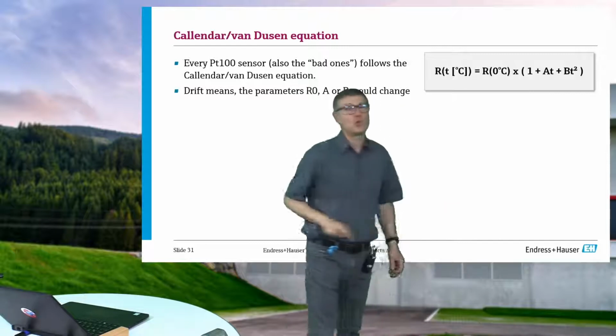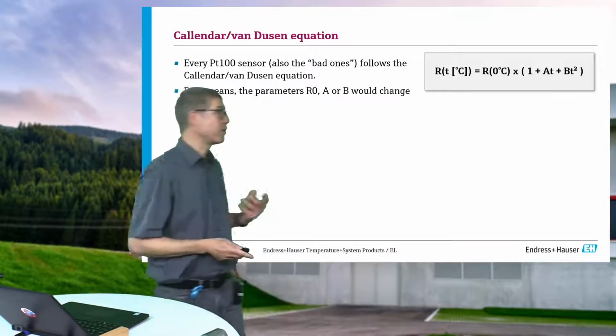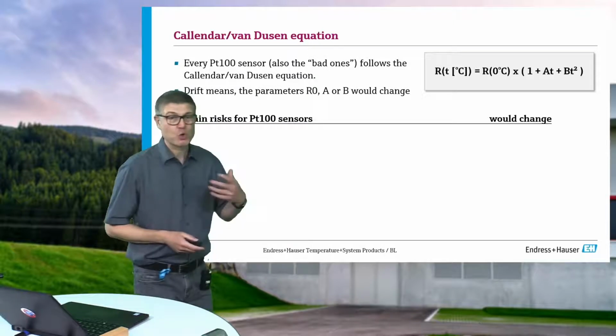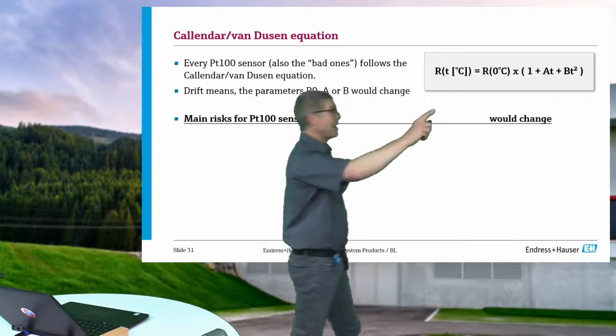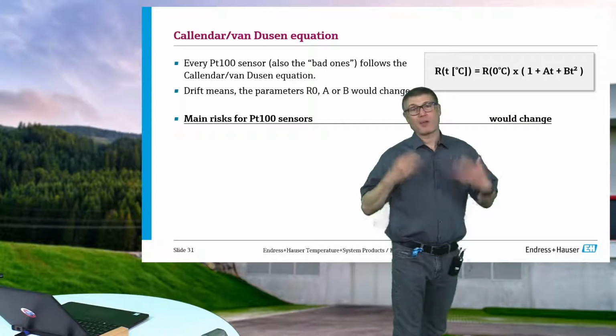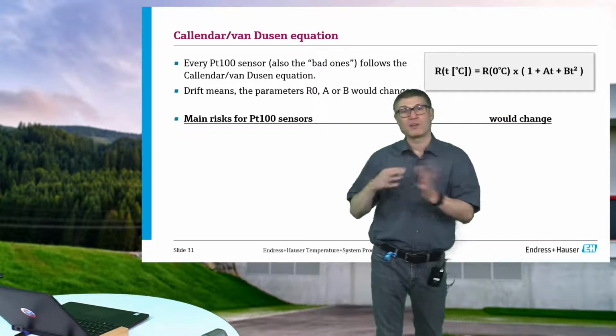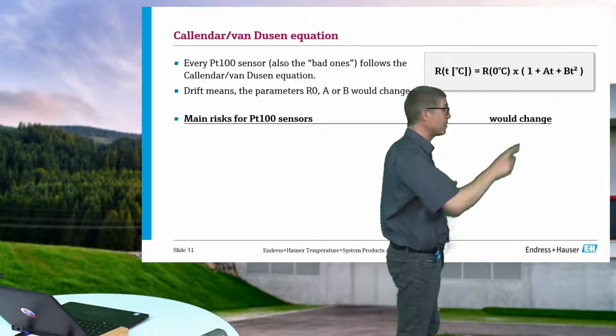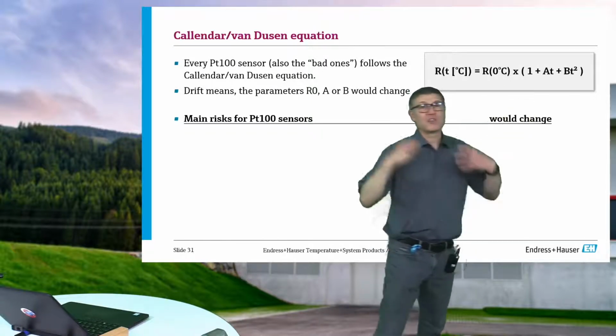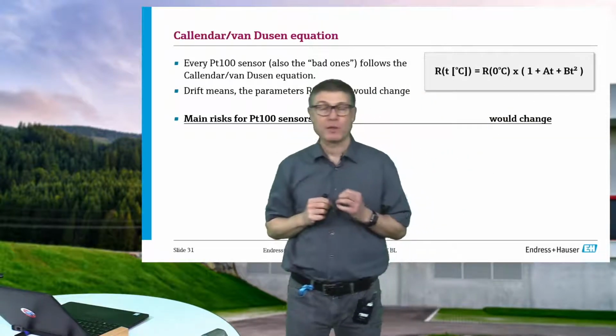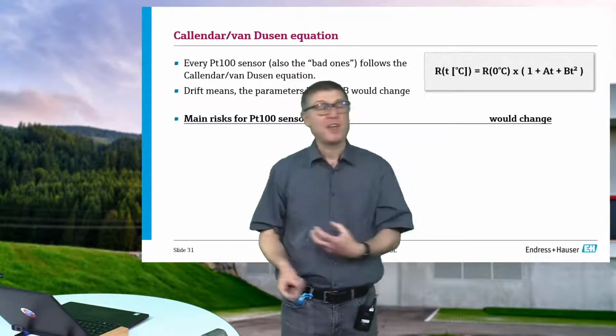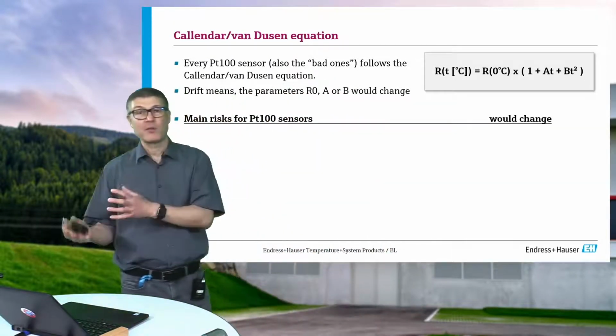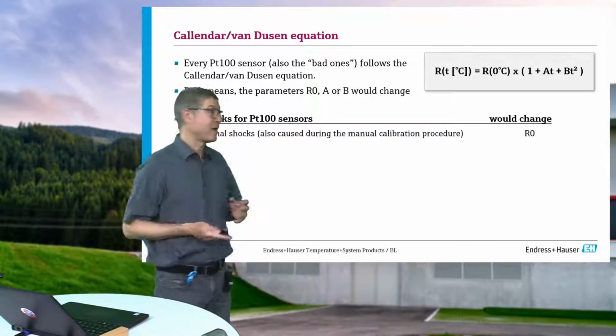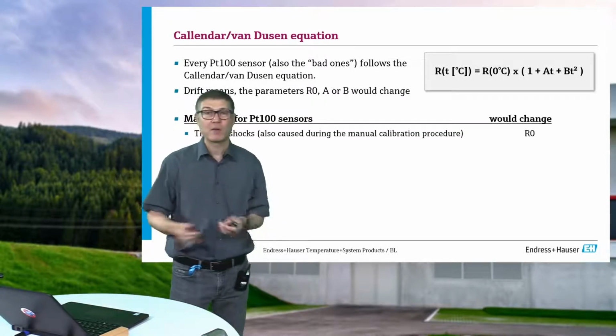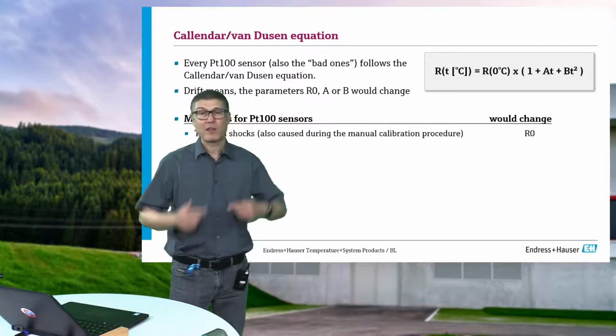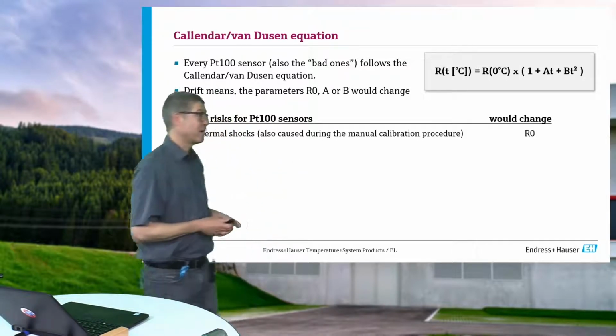PT100, is relating to this formula, which is Callendar-Van Dusen. That means if a sensor is drifting or has a problem, as long as it still works, so it's not broken, not short circuit, it is not possible that only 1 point is affected. If we see a calibration difference at 1 point of the curve, it is not possible that it is accurate somewhere else. And you can for sure invert this statement.